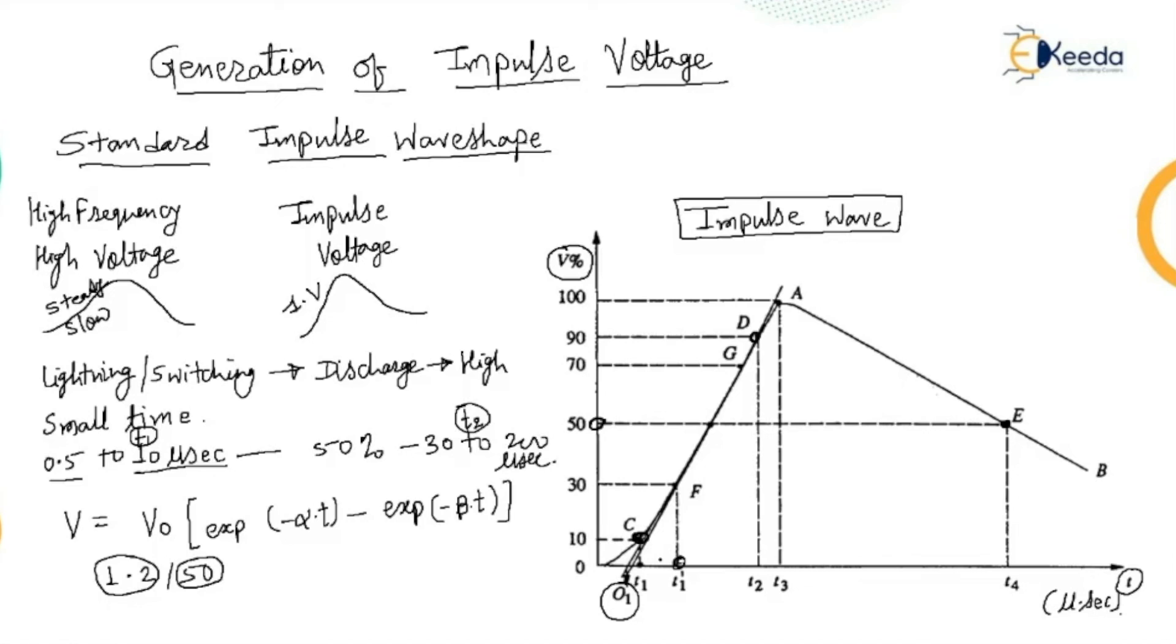As per Indian standards specifications, 1.2 to 50 microsecond wave to be the standard lightning impulse. The tolerance allowed in the peak value is plus minus 3%. So, this is the general idea about the waveshape. Hope you understood the concept related to this standard impulse waveshape.